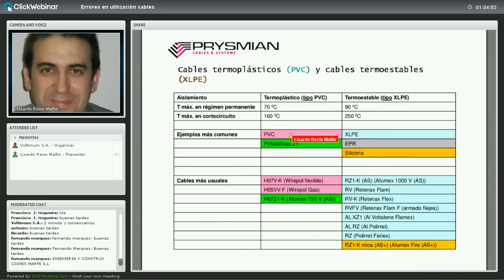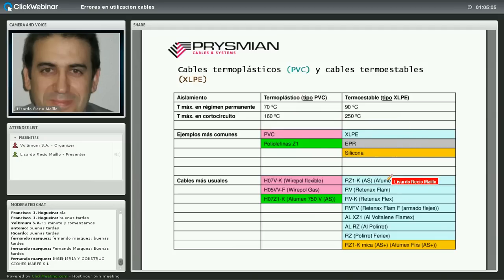Los principales aislamientos de 70 grados son PVC y poliolefinas Z1; los de 90 grados son XLPE, como en los cables tipo RVK y RZ1K de 1000 V, EPR y silicona. Para no equivocarse al hacer cálculos, en la página 22 de nuestro catálogo de baja tensión —disponible en nuestra web— hay una tabla donde se indica qué cables son PVC y cuáles son tipo XLPE, tanto su designación genérica como su nombre comercial.